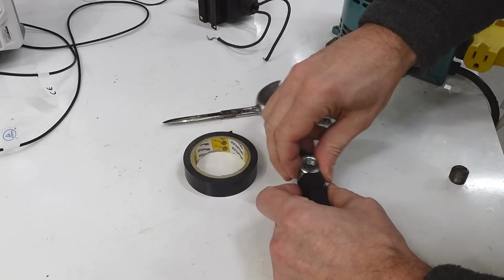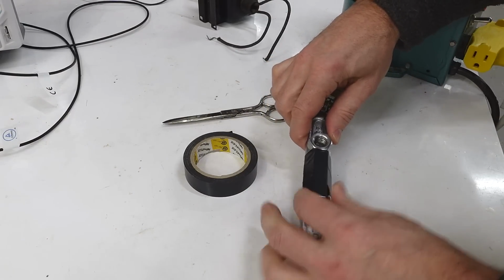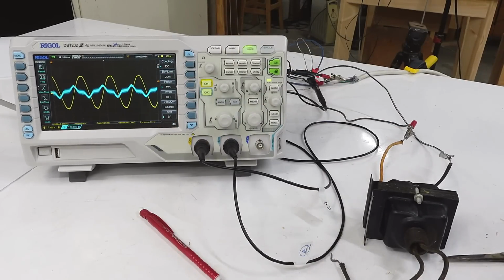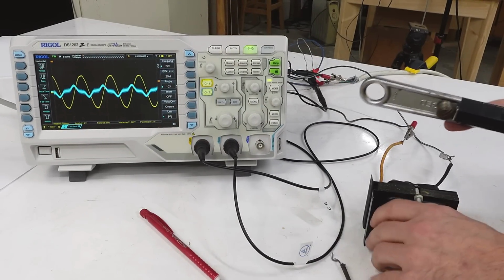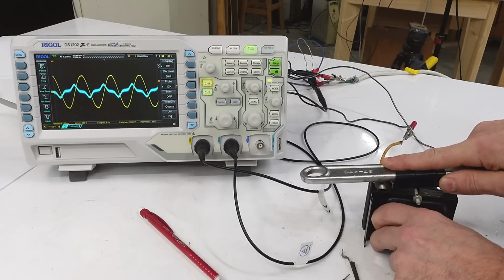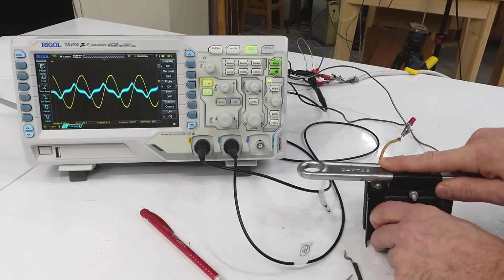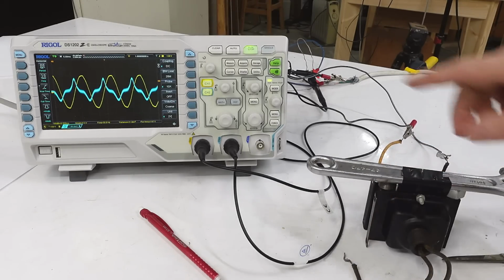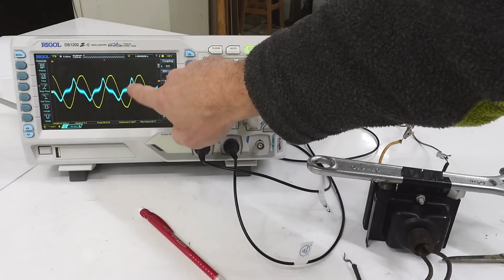These nuts will provide a return path for the flux. Now watch what happens to this current waveform as I put this magnet on the transformer. Notice how it's also getting louder. Now we have quite a bump on one side here, not so much on the other side.